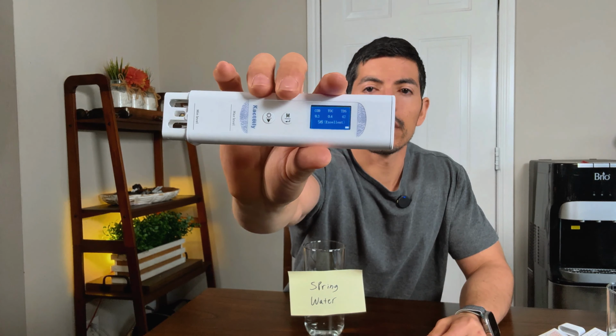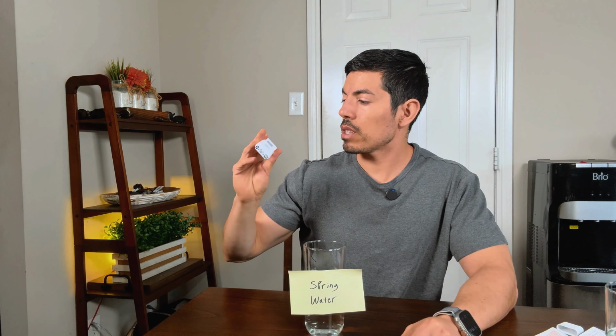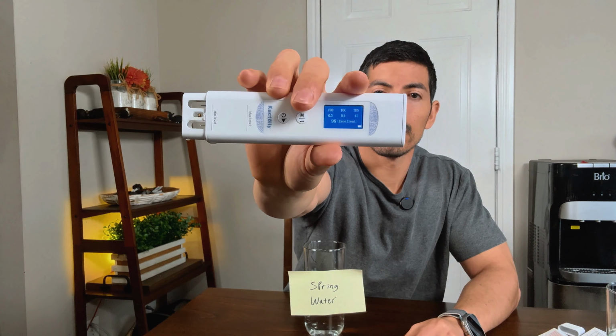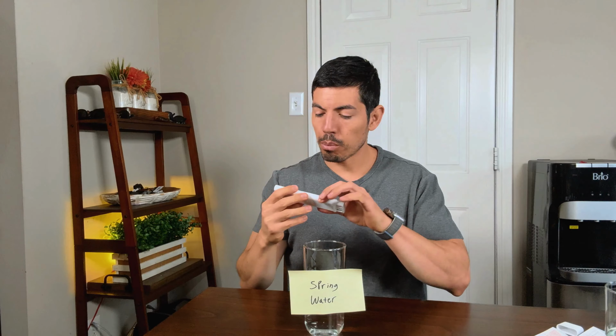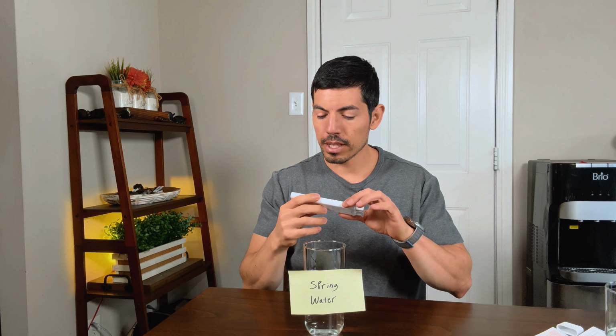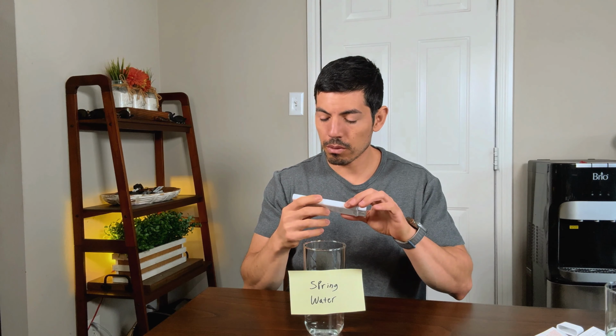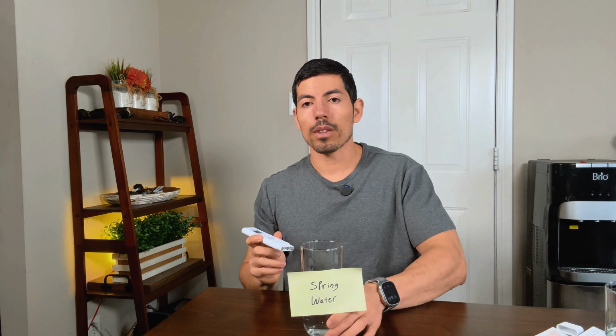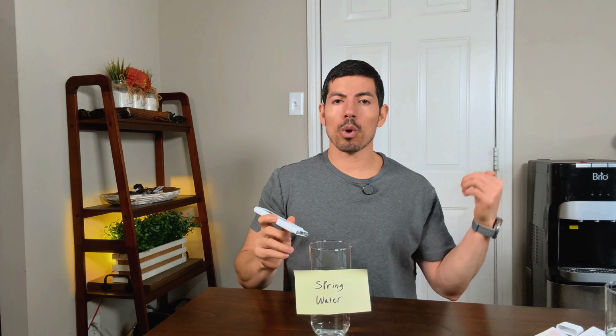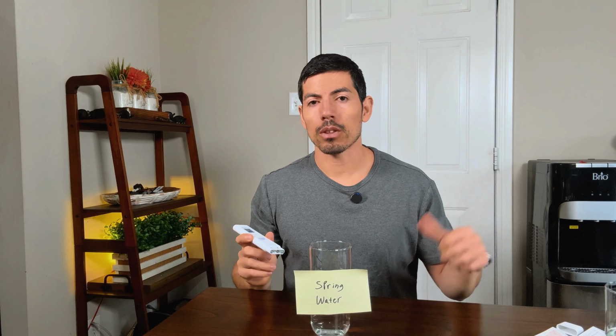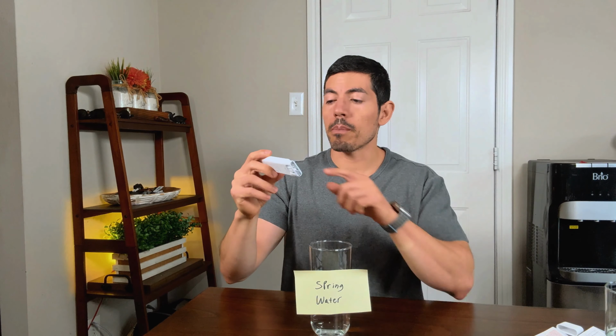So it does give us the COD, TOC, and TDS right on the front screen here. So we have a COD of 0.3, TOC of 0.4, TDS of 42. So again, excellent score with the spring water here. It's actually the spring water I just got from the back right here, the water dispenser. Okay, so those were the main readings.